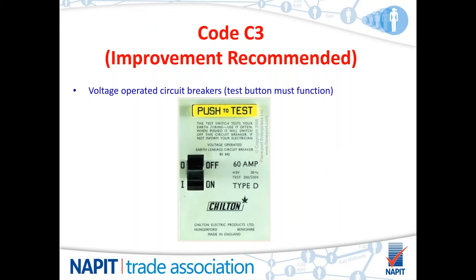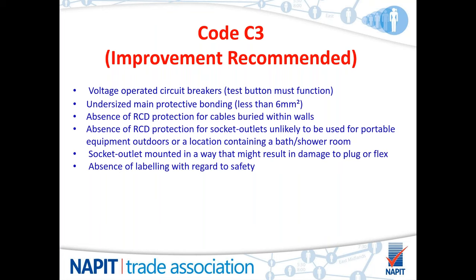Code C3s, improvement recommended. A C3 doesn't necessarily fail the periodic inspection. It could pass as satisfactory. They are just improvements to the installation that are recommended for the customer to take on board. Such things as a voltage-operated circuit breaker. Voltage-operated circuit breakers are of a very old ilk, and really there are no test instruments available to test them efficiently. The only way of testing these is with the test button, and of course that test button must function. Any undersized main protective bonding conductors that are less than 6mm cross-sectional area may get a good Zs, and therefore protective devices will operate.